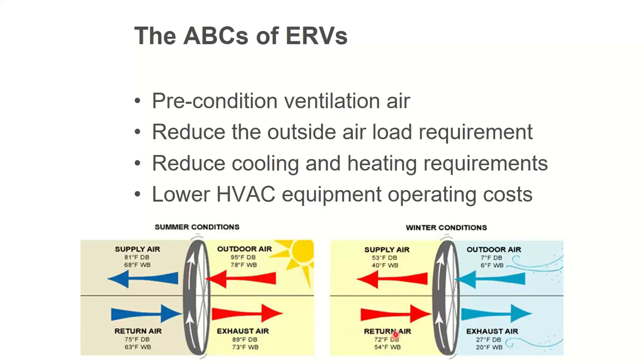Additionally, if it's an enthalpy recovery type ERV, it's going to also do latent energy. So I had 54 wet bulb that was going to exit, and I spin that to the other airstream, and my 6 degree wet bulb coming in turned into 40. So I came in at 6 wet, 7 dry, and I exited the wheel at 40 wet, 53 dry bulb. And then that went into my air handler to be further heated and cooled as needed. But that's starting out. My air handler, my cooling coil, or in this case, probably my heating coil, doesn't know it's a 7 degree day outside. It thinks it's 53 out. It's getting 40 some degrees of free heat to start off with.